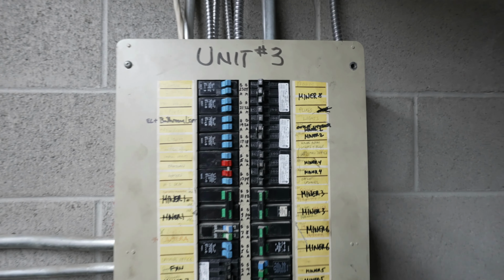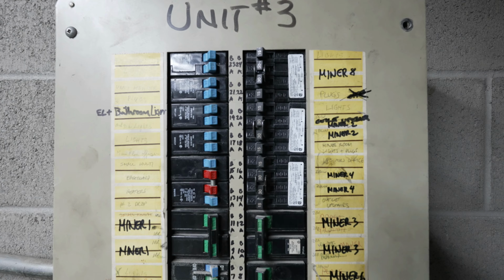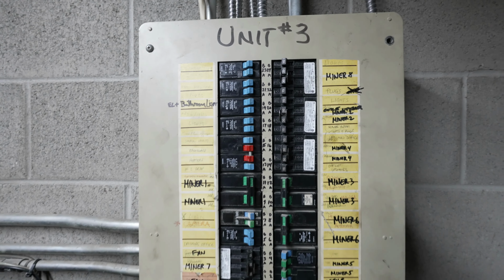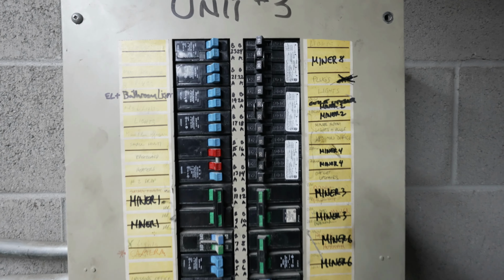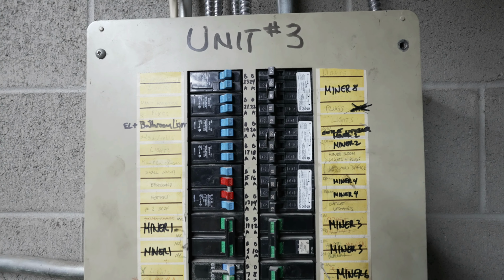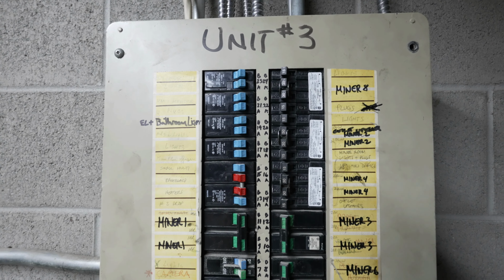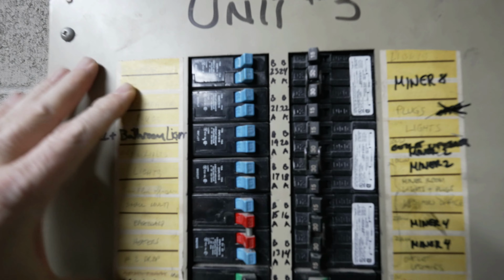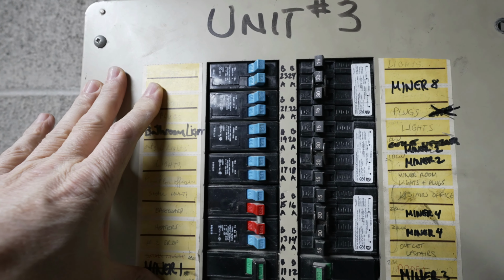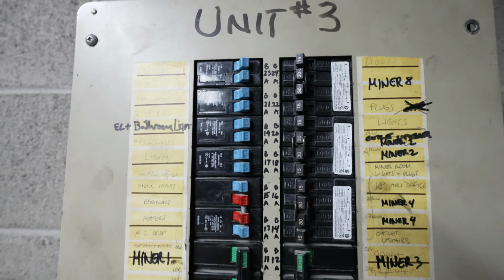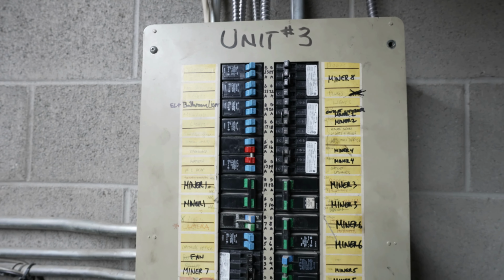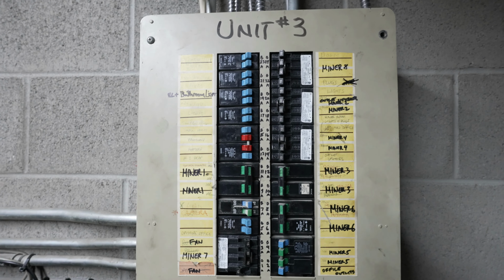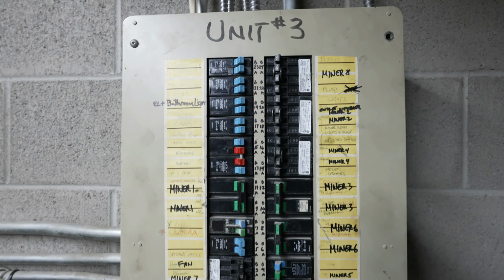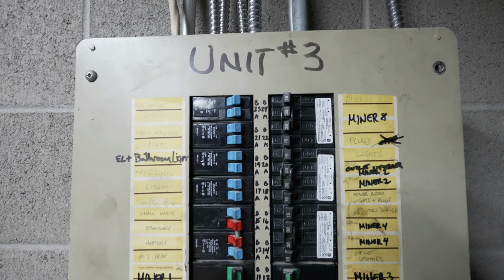We thought we might end up having a problem with that and might have to get a transformer, but I'll be honest, we've had zero issues running at 208 volts. My only recommendation would be to make sure you get the heaviest gauge wires you can for your C13 to C14 cables, or whatever you're using to plug your miners into your PDUs.